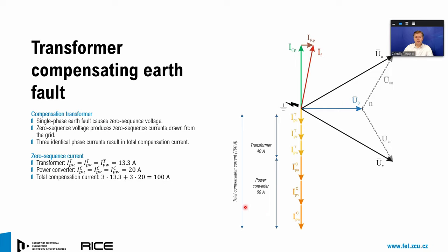Speaking in numbers, the converter is able to generate 20 amps of the compensation current per phase. So it means that 60% of the total compensation current is, in the case of our prototype, produced by the power electronics converter, and the remaining 40% by the transformer. This ratio can be adjusted by the transformer design, so if we need to save more silicon, we can.